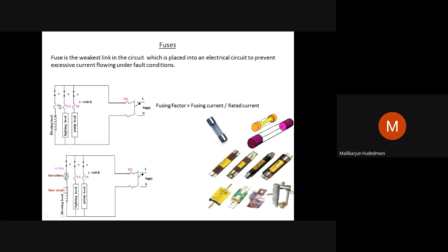And internally I have circuit number 1, circuit number 2, different loads: a pump load, a light load, a heating load. They have some ampere fuse here, 5, 5, 5, etc. If this pump is drawing more than 5 ampere due to internal failure, jam, or mechanical stress, it automatically consumes more current. Then with more than 5 ampere, this fuse will break. Suppose in the bulb holder, water has entered and directly a short circuit has occurred between the holder terminals. So this 5 ampere fuse will break.